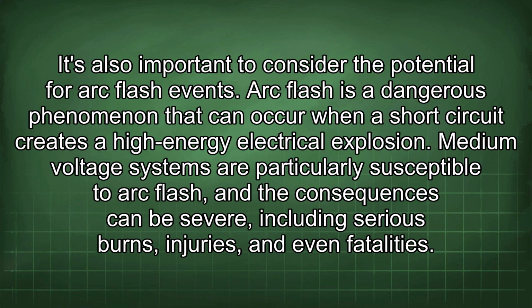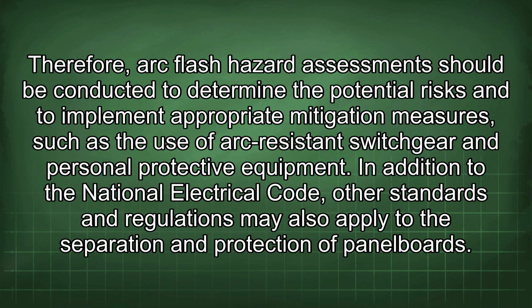It's also important to consider the potential for arc flash events. Arc flash is a dangerous phenomenon that can occur when a short circuit creates a high-energy electrical explosion. Medium voltage systems are particularly susceptible to arc flash, and the consequences can be severe, including serious burns, injuries, and even fatalities. Therefore, an arc flash hazard assessment should be conducted to determine the potential risks and to implement appropriate mitigation measures, such as the use of arc-resistant switchgear and personal protective equipment.